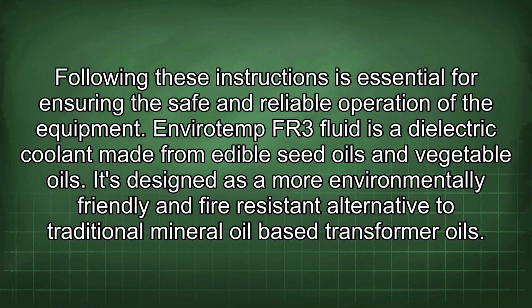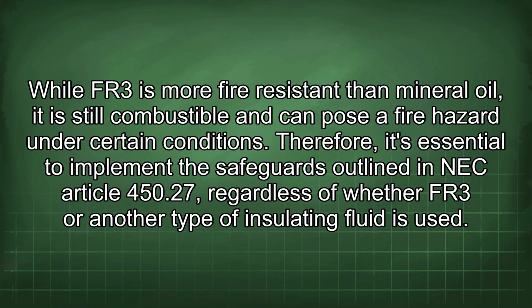Envirotemp FR3 fluid is a dielectric coolant made from edible seed oils and vegetable oils. It's designed as a more environmentally friendly and fire-resistant alternative to traditional mineral oil-based transformer oils. While FR3 is more fire-resistant than mineral oil, it is still combustible and can pose a fire hazard under certain conditions. Therefore, it's essential to implement the safeguards outlined in NEC Article 450.27 regardless of whether FR3 or another type of insulating fluid is used.